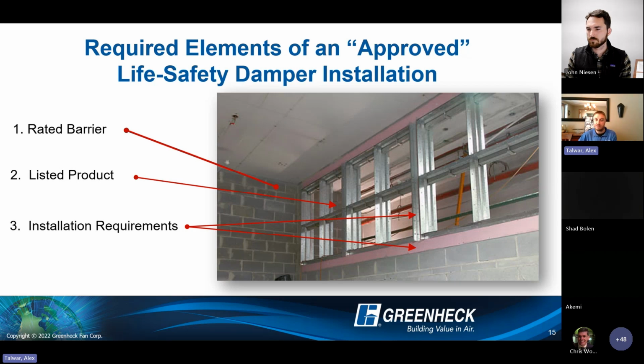So, you need to pick the correct product for the correct barrier, right? You need to have some type of rating, fire rating, smoke rating, whatever it is, understand what the barrier is and what type of product is required. If you need a fire damper, smoke damper, both, right? It has to be a listed product. So that's number two. It's got to be a UL certified product. That is another requirement of the International Building Code, in fact. And then none of that does you any good unless you are installing per the manufacturer's UL approved installation instructions.